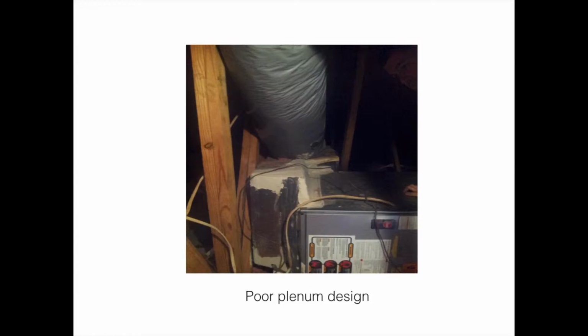There's a lot going wrong in this picture. The trusses are obviously in the way of the HVAC equipment, but it's not the builder's responsibility to move those trusses. The HVAC company probably could have installed the unit better and put the unit parallel with the trusses instead of perpendicular. I'm not sure of the exact situation as to why they didn't, but you can tell that this really affects air distribution, comfort, as well as the life of the equipment.